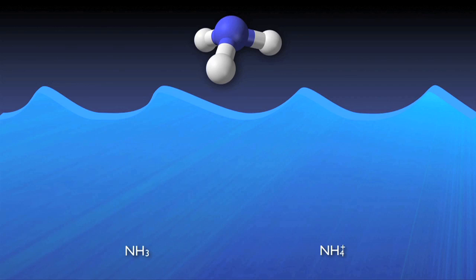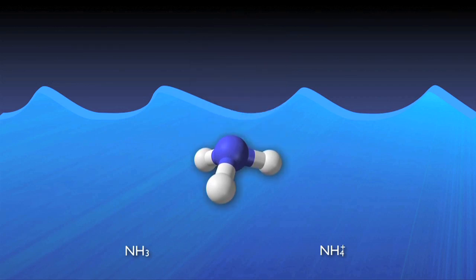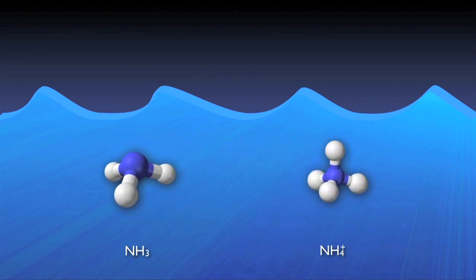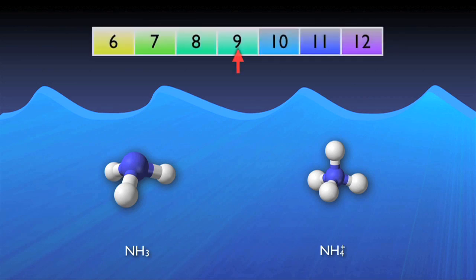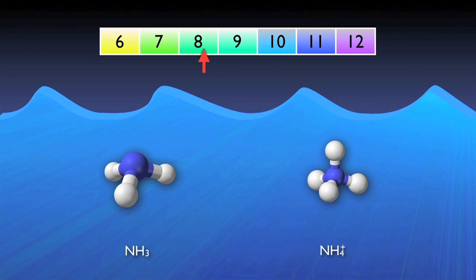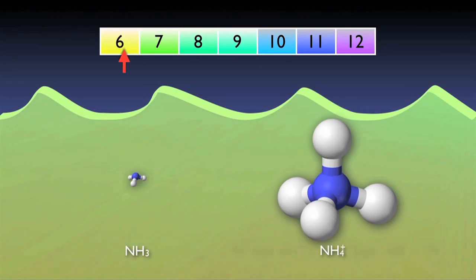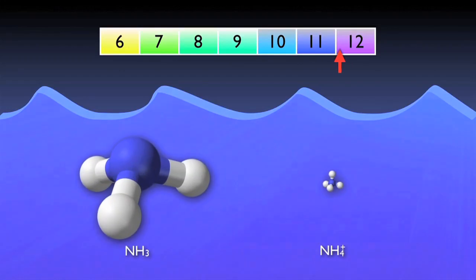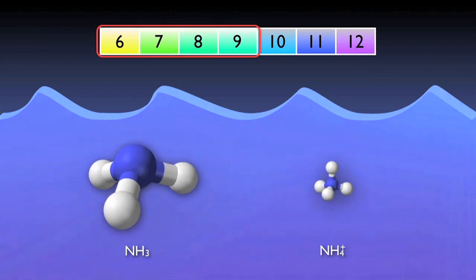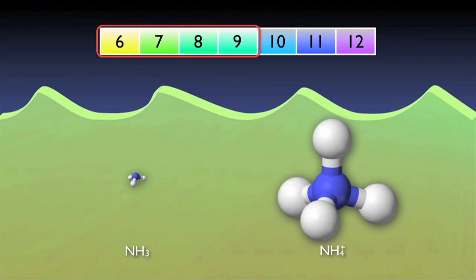First, as a natural reaction in an aqueous solution, the vast majority of the organic nitrogen immediately hydrolyzes into ammonia. Most of this ammonia automatically converts to the ionic form ammonium. The equilibrium between the gaseous and ionic forms of ammonia is heavily impacted by the pH of the water. A more acidic solution will favor the ionic form ammonium; a more basic solution will favor the gaseous form ammonia. Since wastewater typically ranges between a pH of 6 and 9, almost all of the ammonia will be in the ionic form.